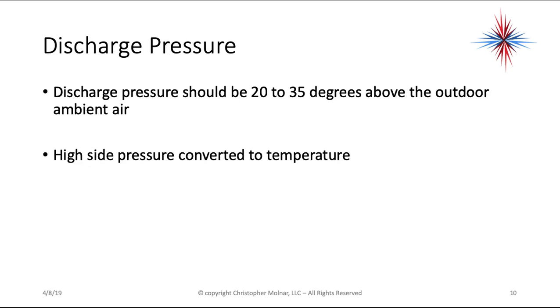Discharge pressure should be 20 to 35 degrees above the outside air temperature. Again, that's the high side pressure converted to temperature.